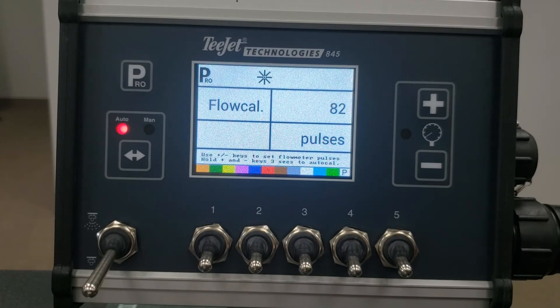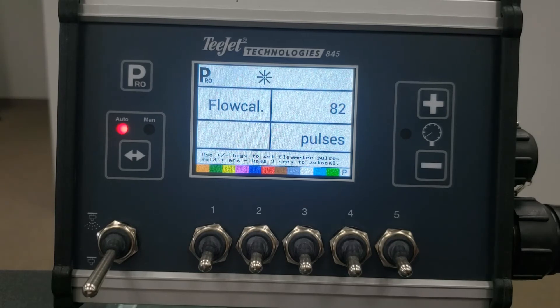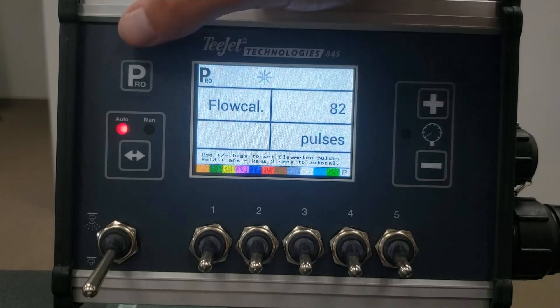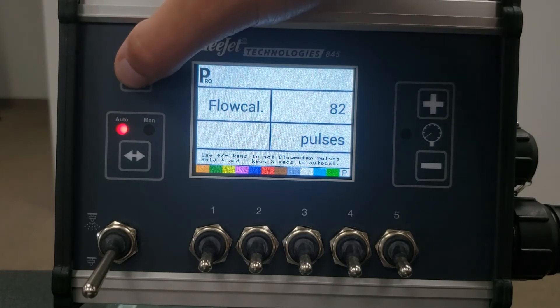The next step is where you enter the flow meter calibration number. This is normally found on the flow meter sensor cable. The default is 82 pulses per liter, which is the calibration number for the 801 flow meter. The calibration number is entered as pulses per liter, regardless of what units were selected in the first step. Press the Pro key to move to the next step.